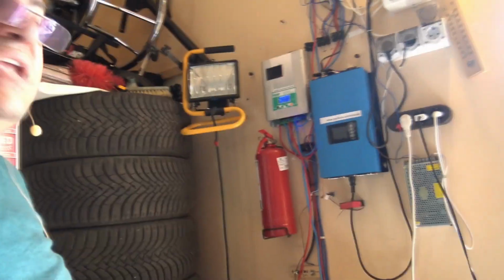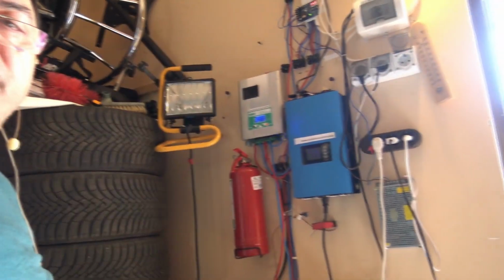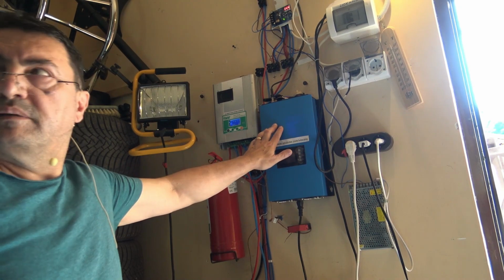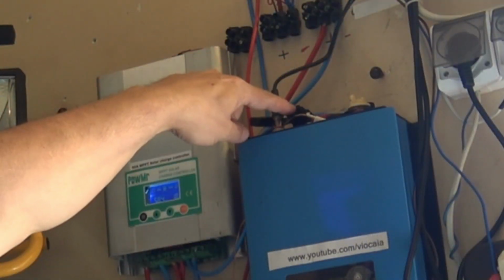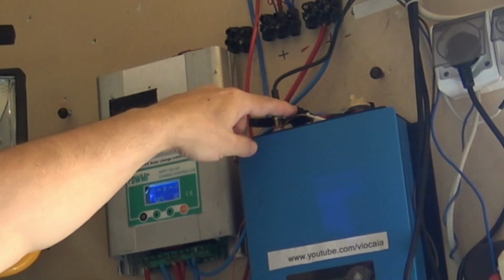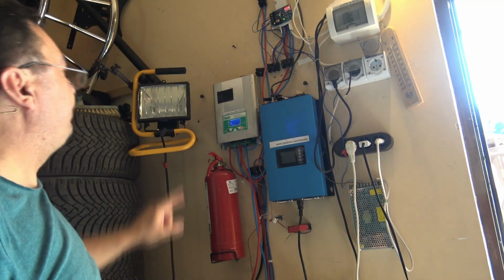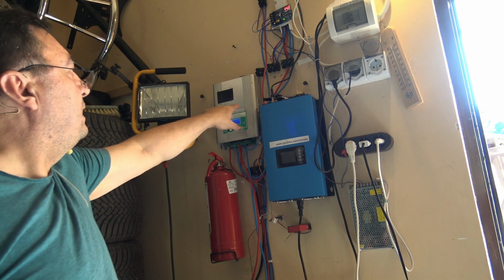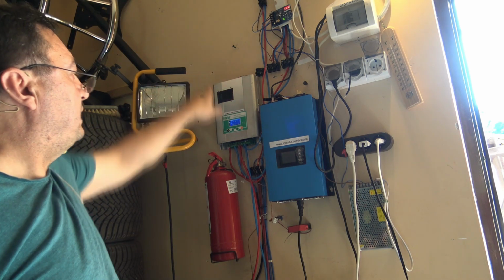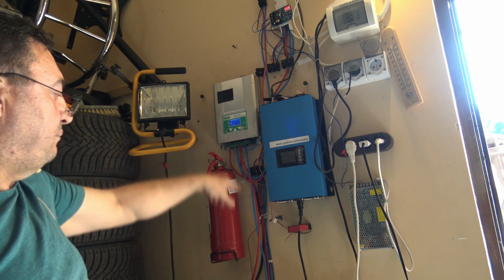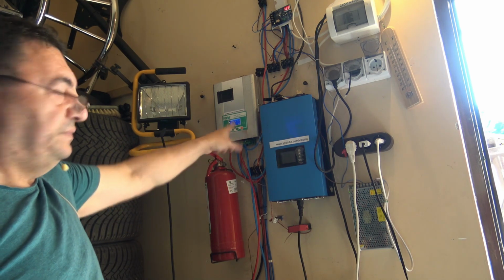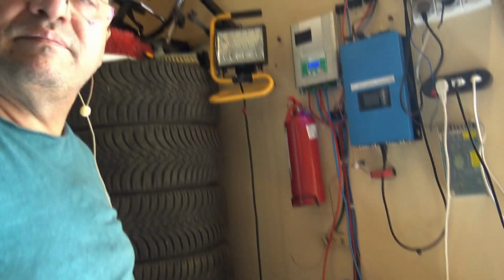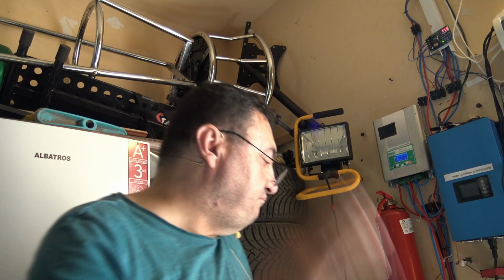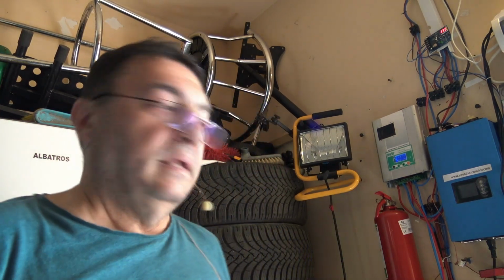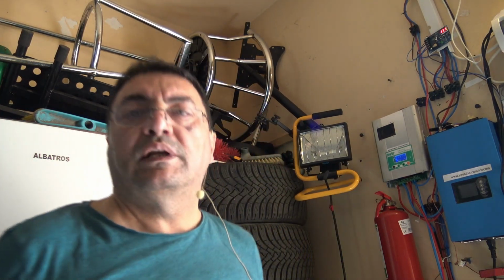And just in case something wrong happens with my inverter - it happened before, some MOSFETs burned or something - there I have a 40 amps fuse, so that one blows instantly. Inside here are also 60 amps fuses for the solar and something more for the output, but I don't want to talk about that anymore. Here, 40, 40 and 40 amps fuses. These guys blow up instantly. Nothing wrong can happen, absolutely nothing.